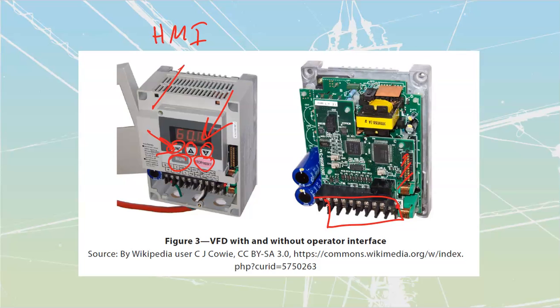By the way, for those of you that have never dealt with these motors or drives before, we commonly have U, V, and W utilized to indicate the ABC on my load. And then coming in on my lines, I'm going to commonly have L1, L2, L3, or sometimes they'll have ABC, but it's pretty standard. That's going to be L1, L2, L3 on the incoming, and U, V, W on the outgoing.